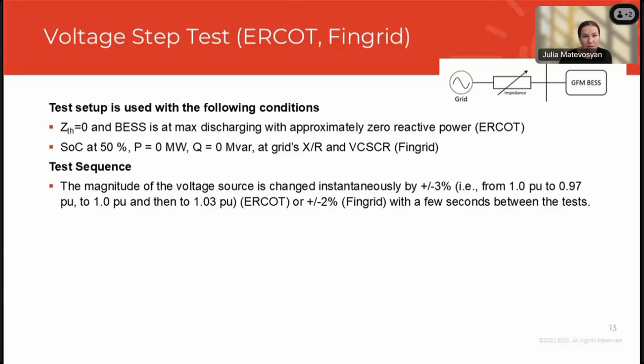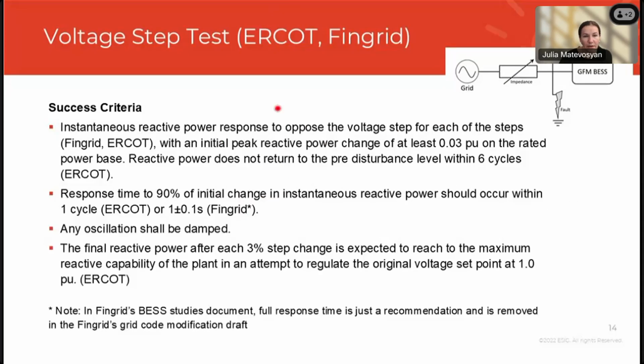Again, there is a step test defined in ERCOT and FinGrid at different short circuit level conditions, different dispatch of a tested device, and magnitude of the voltage source is changed instantaneously plus minus 3% in ERCOT and plus minus 2% in FinGrid, with a few seconds between the tests.